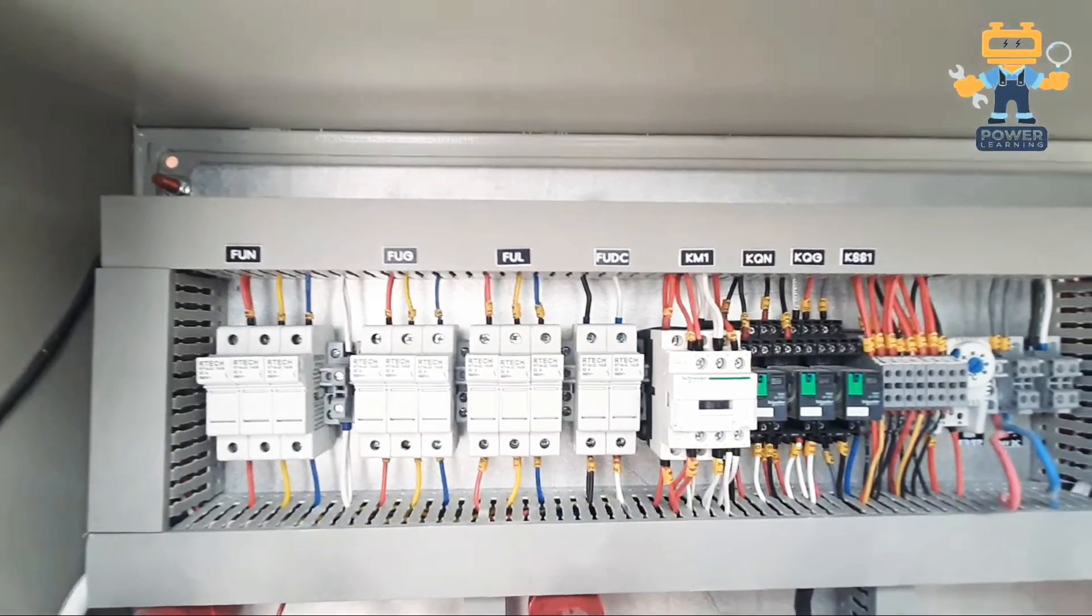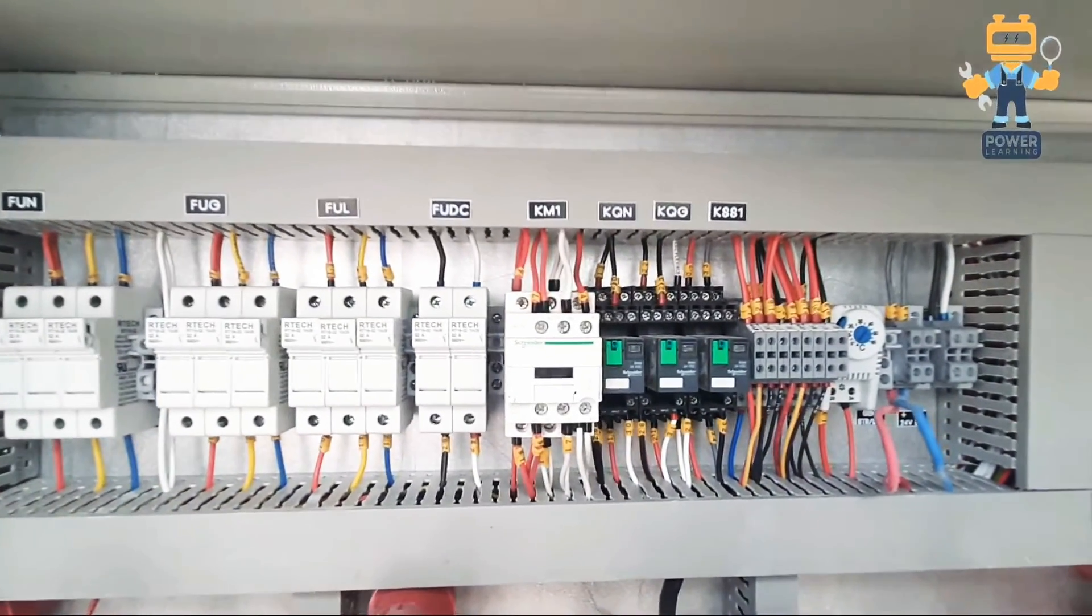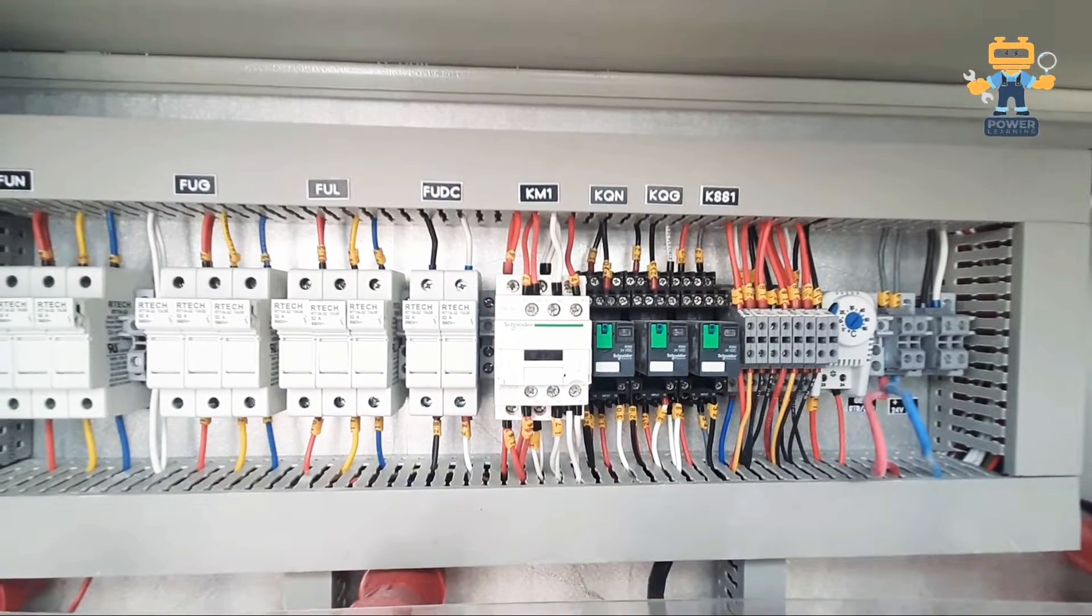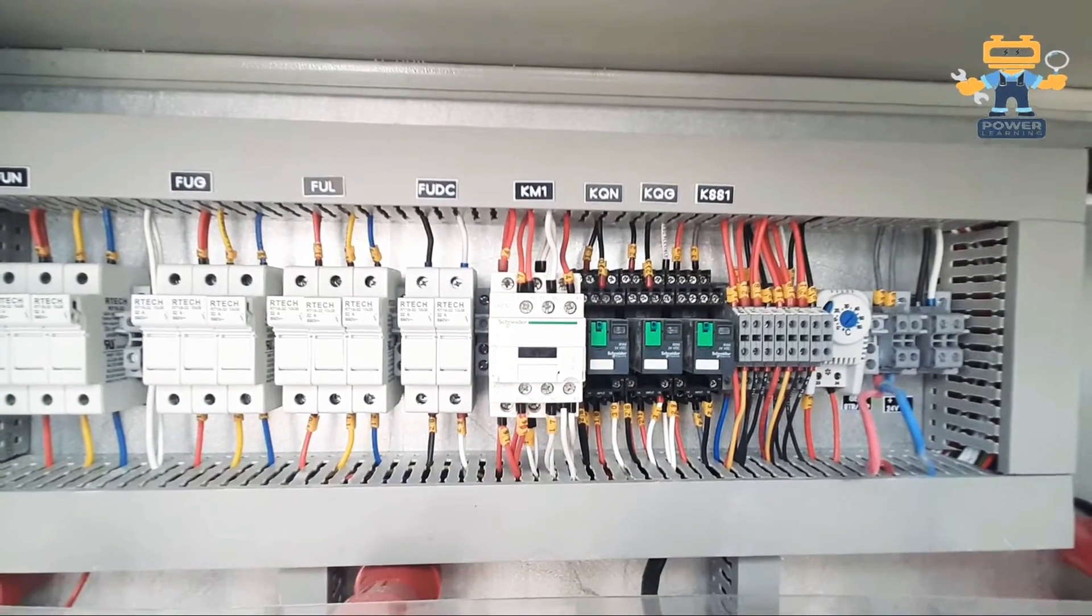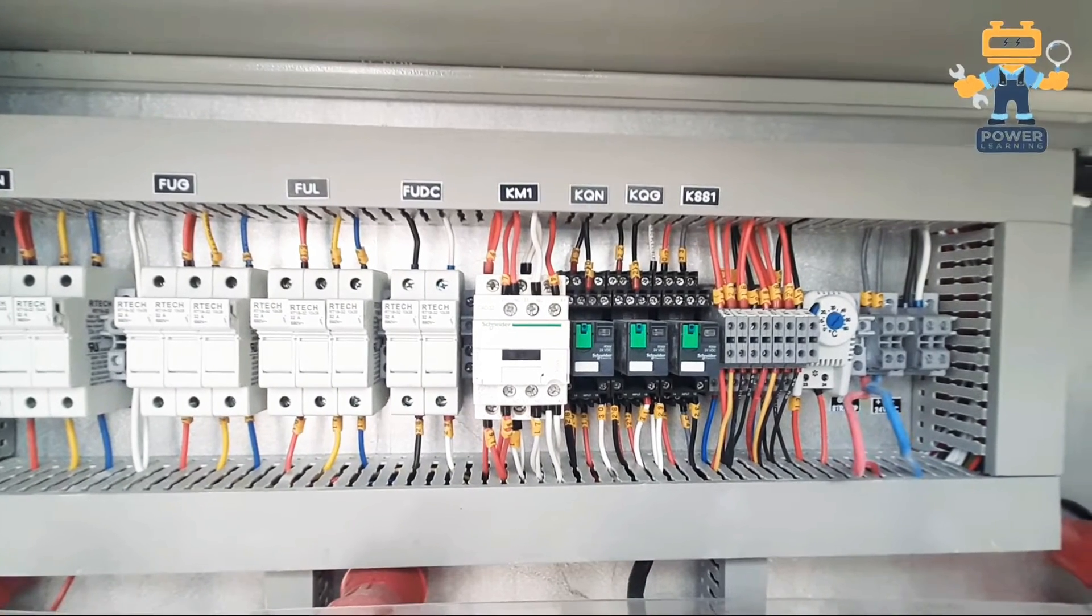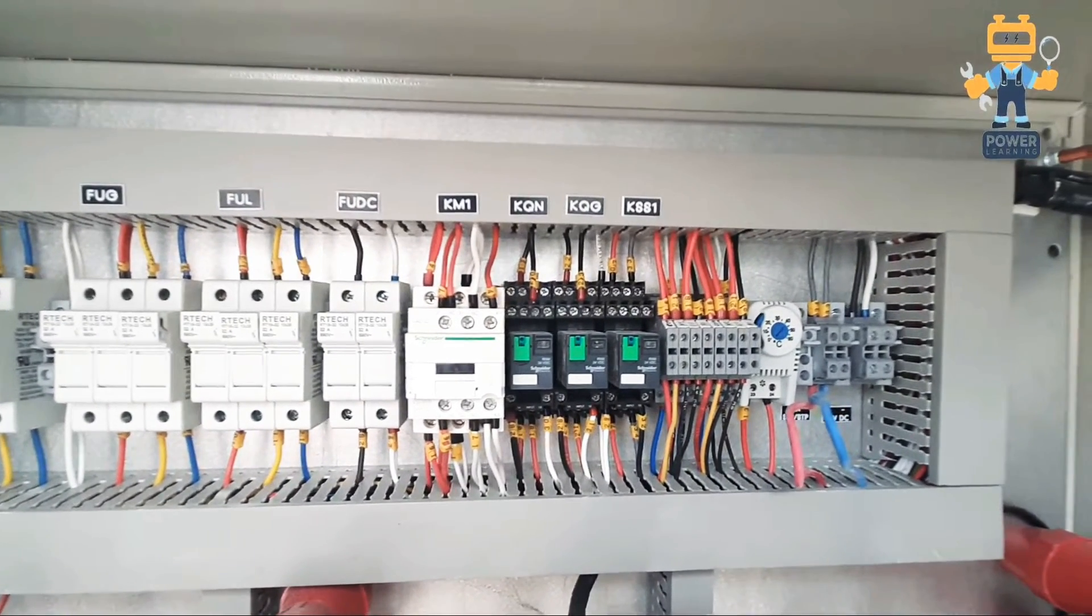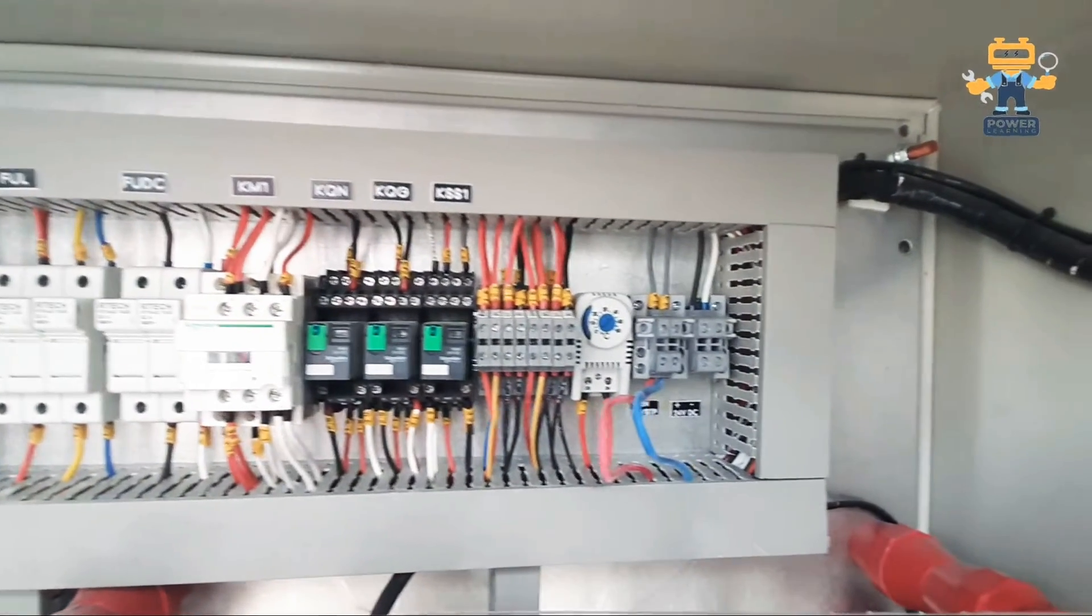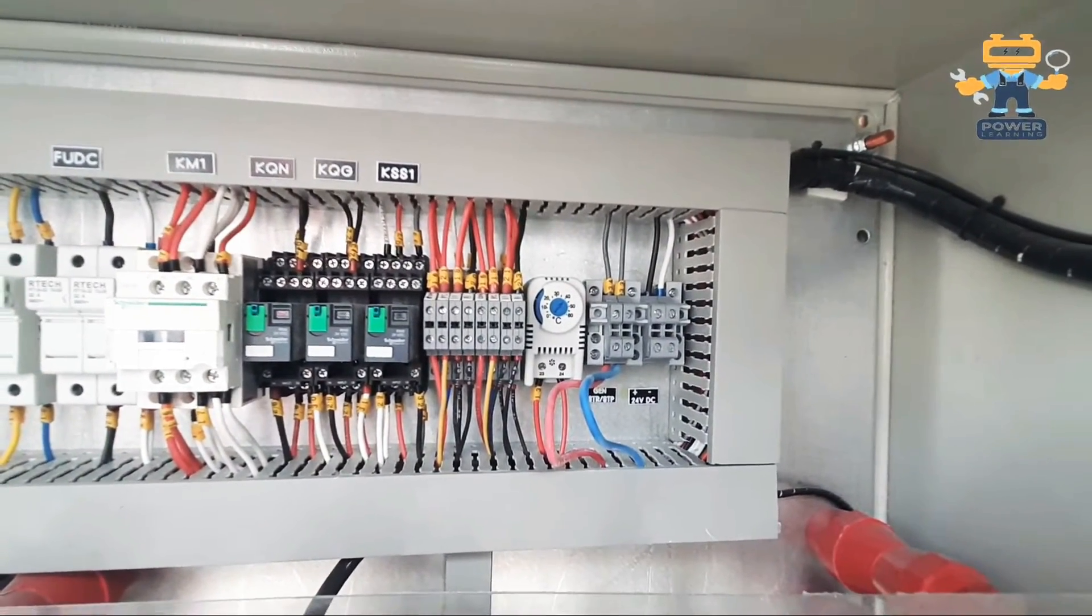KM1 is our main contactor for electrical interlock between two supplies. KQN, KQG, KSS1, these are our three relays which are controlled by the ATS controller.